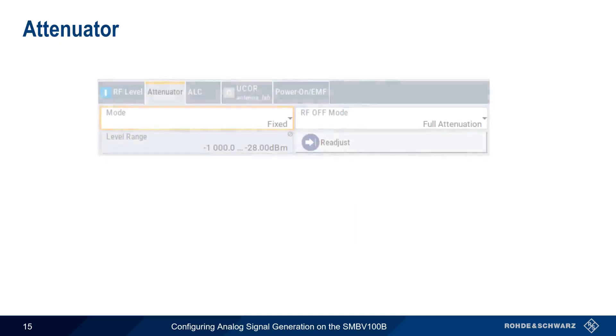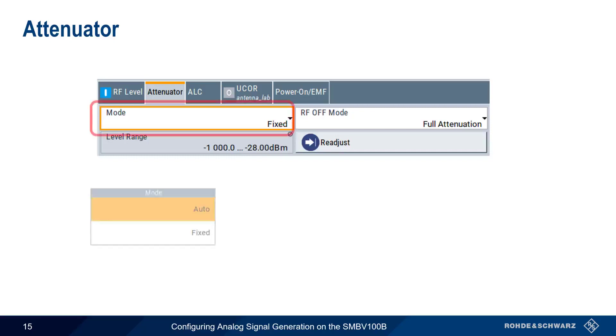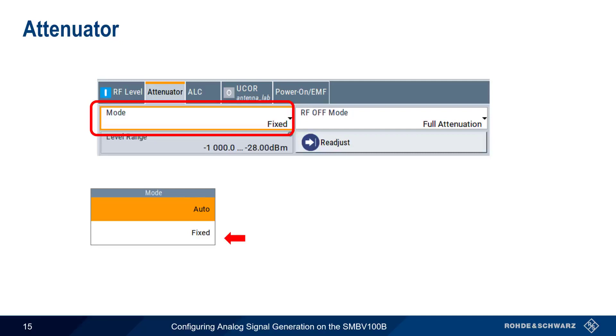One of the ways that the level performance of the SMBV can be improved is through its built-in electronic step attenuator. There are several cases where using attenuation is beneficial, such as when testing a DUT under low signal-to-noise conditions. There are two modes for the attenuator. In auto mode, the generator automatically adjusts the attenuation of the RF output signal. Whereas in fixed mode, the attenuation remains constant. Fixed attenuation values are required if you need uninterrupted level settings with a constant VSWR, and you'll see different level ranges depending on which mode you choose.